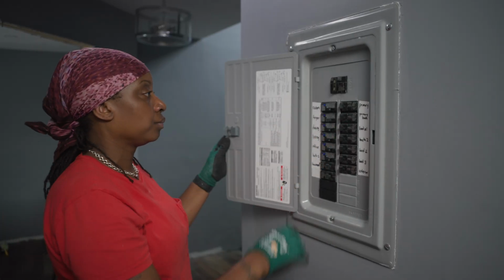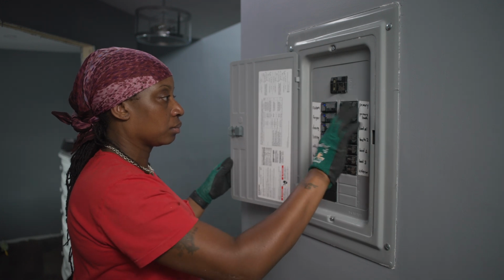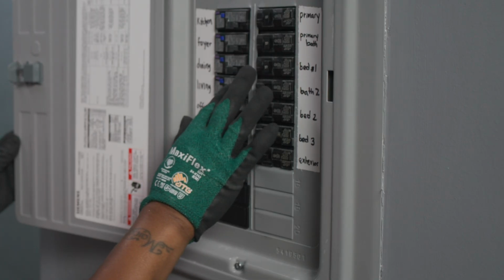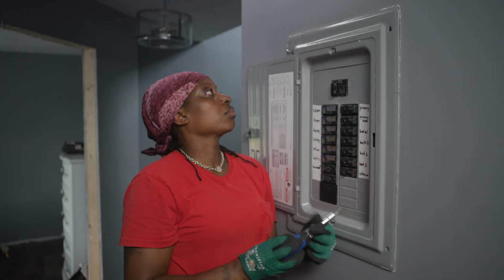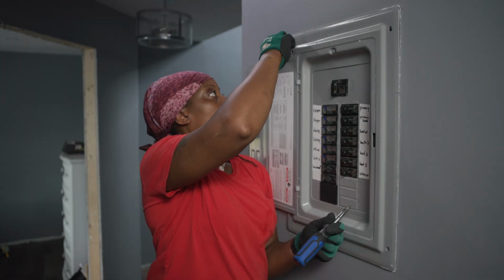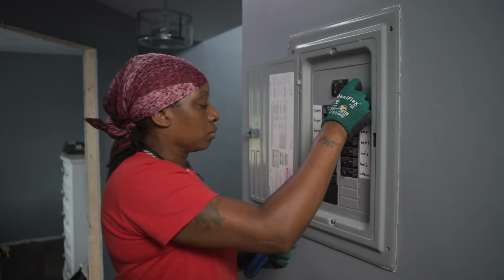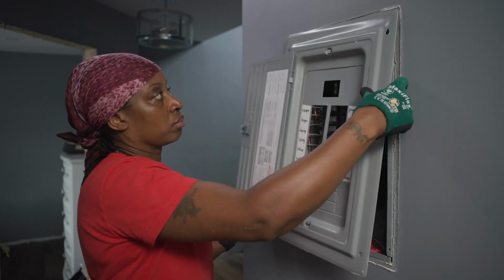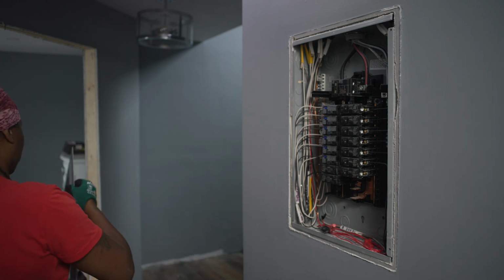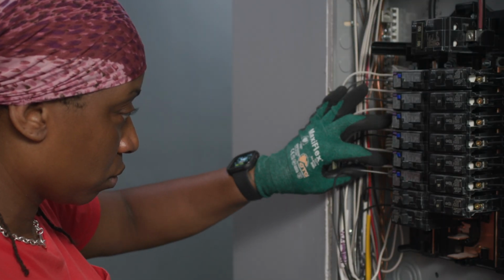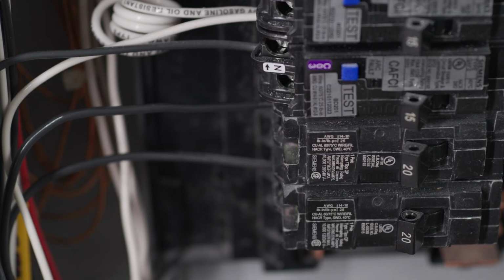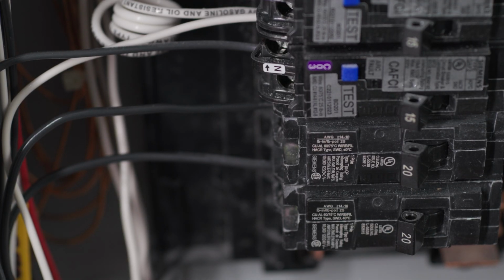Next, turn off the main breaker and each of the individual circuit breakers. To access the breakers, you need to remove the entire breaker panel cover. Remove each of the screws, then pull the cover off and set it aside. Now you are ready to pull the circuit breakers you want to be removed out of its slot. These breakers must be discarded and not reused.